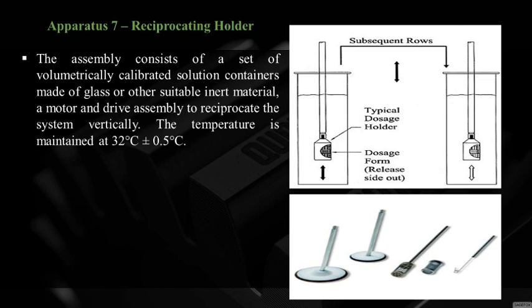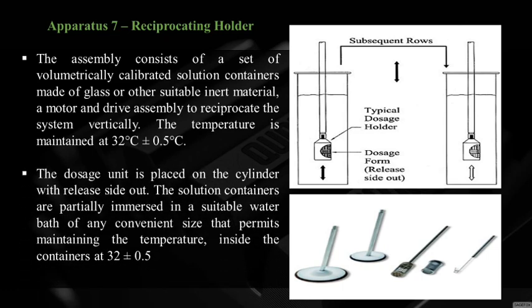Apparatus 7 — Reciprocating Holder: assembly consists of volumetrically calibrated solution containers made of glass or suitable inert material, a motor, and a drive assembly to reciprocate the system vertically. Temperature maintained at 32 ± 0.5°C. The dosage unit is placed on the cylinder with release side facing out. Solution containers are partially immersed in a water bath to maintain temperature at 32 ± 0.5°C.